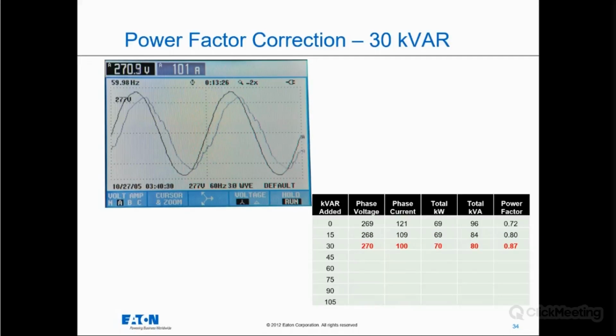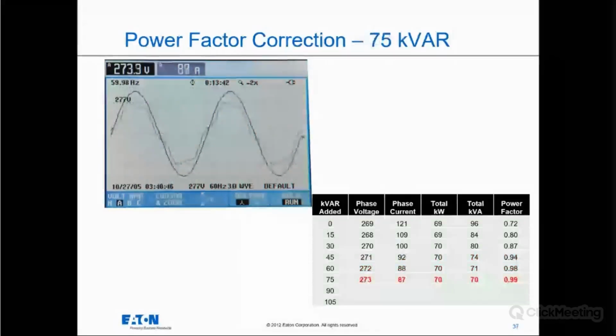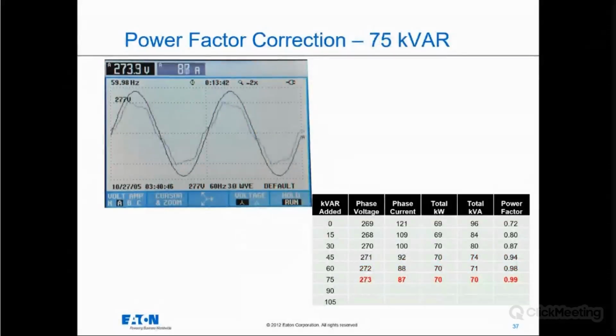We started at a 0.72. We're at 0.87. We're at 0.94 now. We're at 0.98. We're at 0.99. So we're almost to unity. And now we can see our phase current has dropped from 121 down to 87. We can see our kVA has dropped from 96 to 70. Our power factor is obviously improved almost to unity. And our phase voltage has actually gotten a little bit better as well, which again is a side benefit.